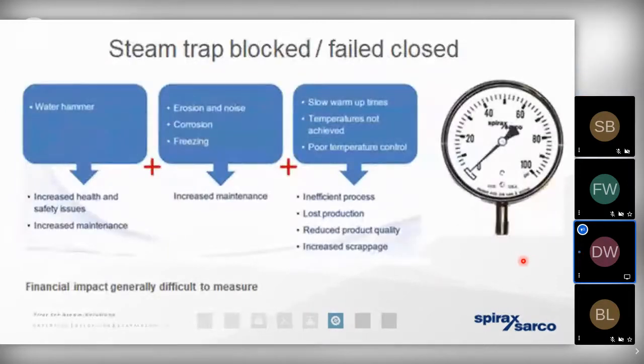But of course, traps can and will fail in the closed position. And that's very difficult to quantify in financial terms. And a failed steam trap is going to have a different impact depending upon what we're talking about. If we're talking about a steam trap that's failed behind a heat exchanger, behind a process, that's going to be very easy to identify because the production manager is going to be shouting at the maintenance team pretty quickly. But if we consider a steam trap that could be failed where it's required to remove the distribution losses, well, we may not be aware of that.